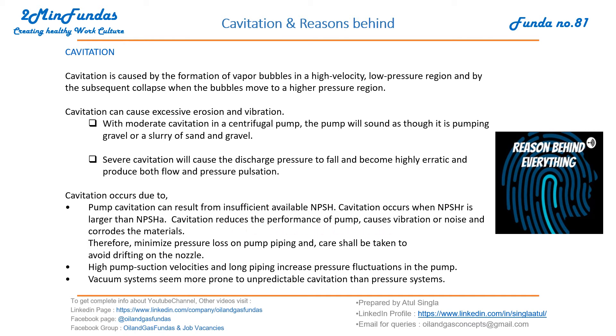Cavitation reduces the performance of the pump, causes vibration, noise, and erosion of material. Therefore, minimize pressure loss on pump piping, and care shall be taken to avoid drifting of the nozzle. That's why the suction line should be minimum in length. High pump suction velocities and long piping increase pressure fluctuation in the system. High velocity and low pressure regions will be there because of long pipe between source and destination point, causing cavitation.